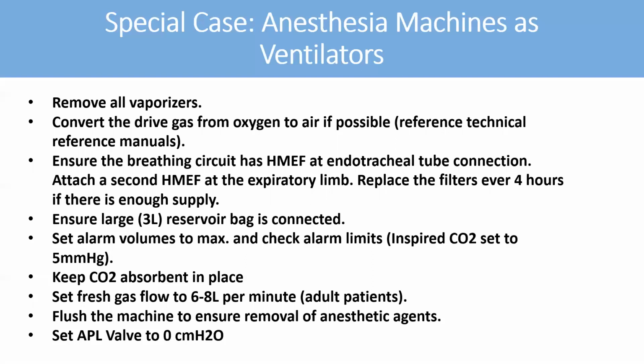Set the alarm volume to maximum. Check the alarm limits, CO2 setting, all of this. Keep the CO2 absorbent in place. Set the fresh gas flow somewhere from 6 to 8 liters for an adult patient. Always flush the machine, remove the anesthesia agent, and set the APL valve at 0, because you want to make sure the circuit is breathing according to that particular range.